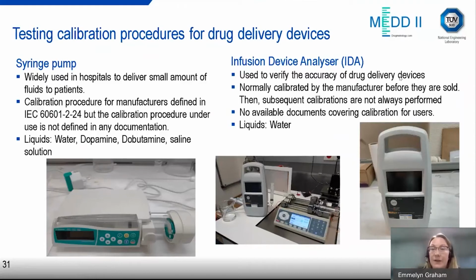Another device that we're using is an infusion device analyzer, and this is used to verify the accuracy of drug delivery devices. They're normally calibrated by the manufacturer before they are sold, and then subsequently calibrations may not be performed, and there's no available documents covering the calibration for users.